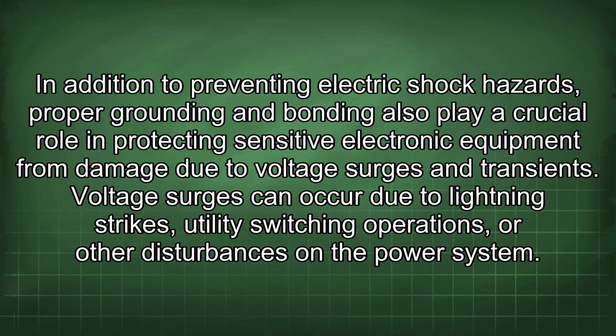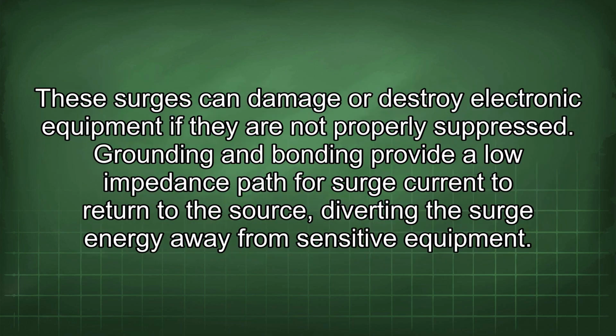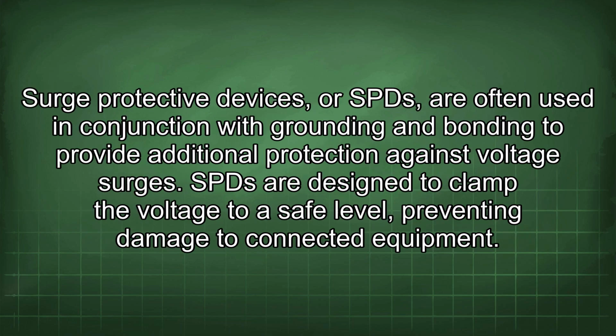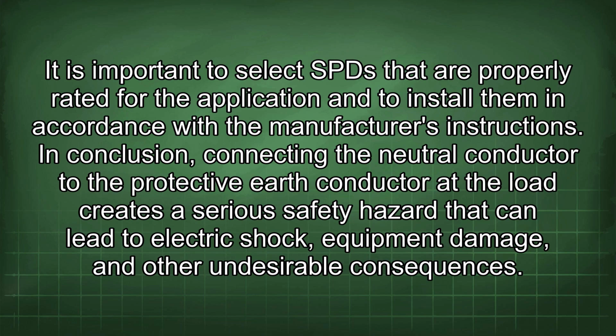Voltage surges can occur due to lightning strikes, utility switching operations, or other disturbances on the power system. These surges can damage or destroy electronic equipment if they are not properly suppressed. Grounding and bonding provide a low impedance path for surge current to return to the source, diverting the surge energy away from sensitive equipment. Surge protective devices, or SPDs, are often used in conjunction with grounding and bonding to provide additional protection against voltage surges. SPDs are designed to clamp the voltage to a safe level, preventing damage to connected equipment.